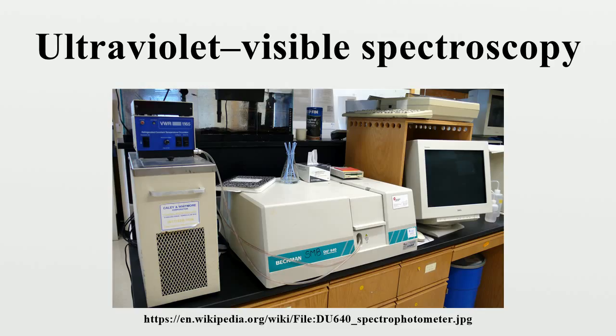The instrument used in ultraviolet-visible spectroscopy is called a UV-Vis spectrophotometer. It measures the intensity of light passing through a sample; the ratio is called the transmittance and is usually expressed as a percentage. The absorbance is based on the transmittance. The UV-Vis spectrophotometer can also be configured to measure reflectance, in which case it measures the intensity of light reflected from a sample. The basic parts of a spectrophotometer are a light source, a holder for the sample, a diffraction grating in a monochromator or a prism to separate the different wavelengths of light, and a detector.